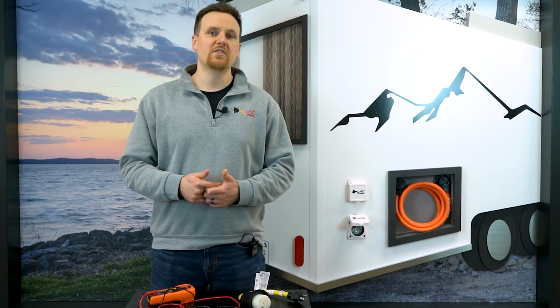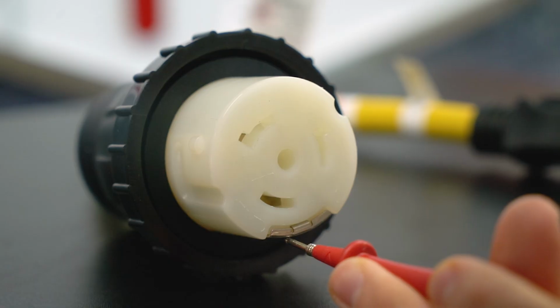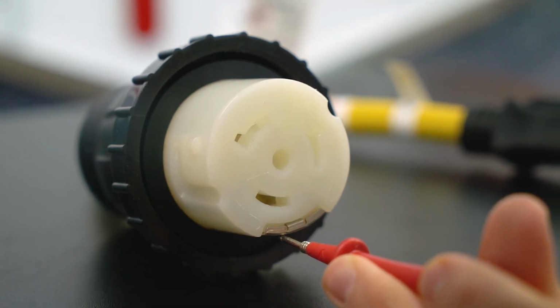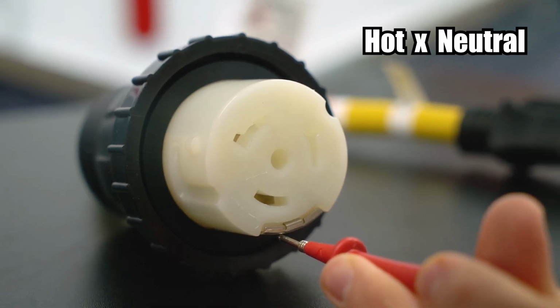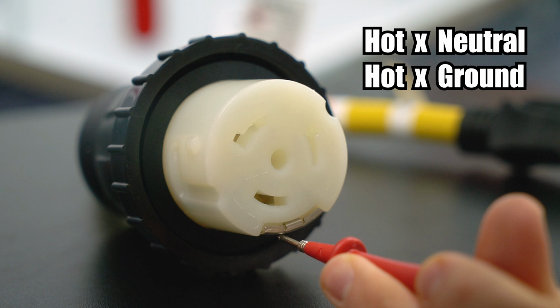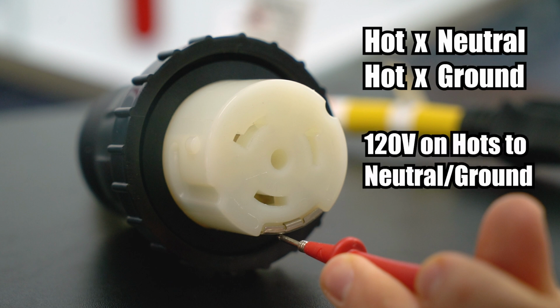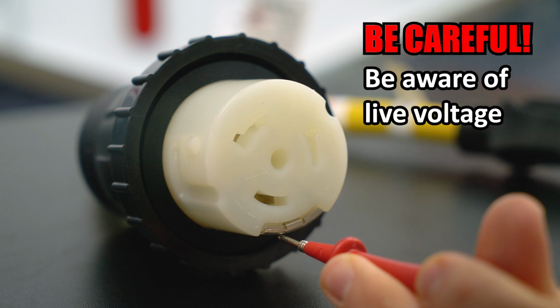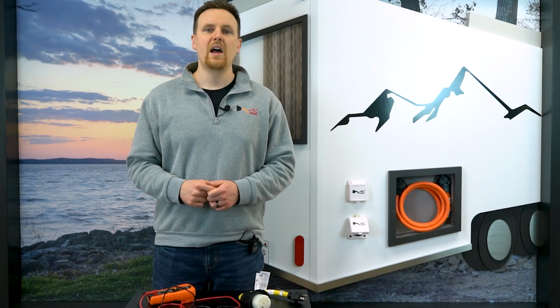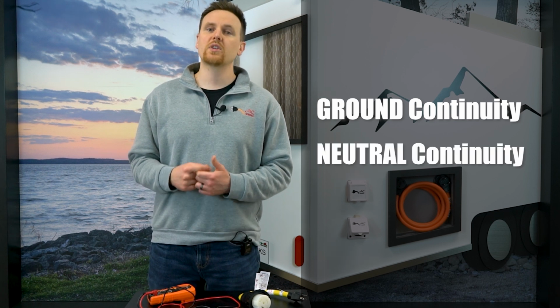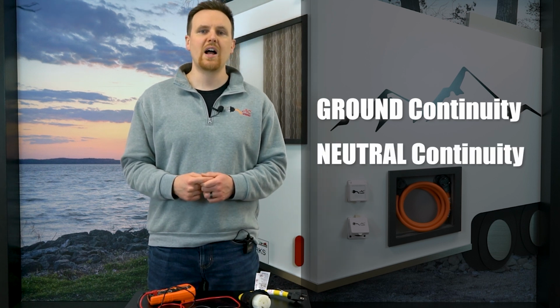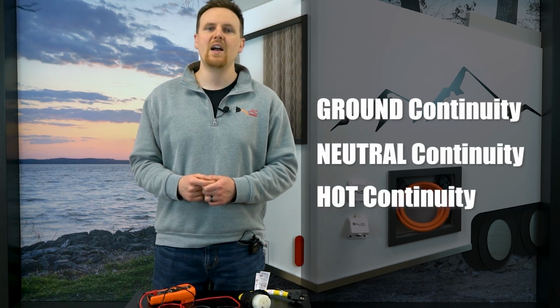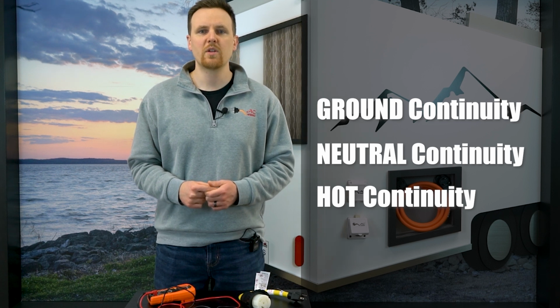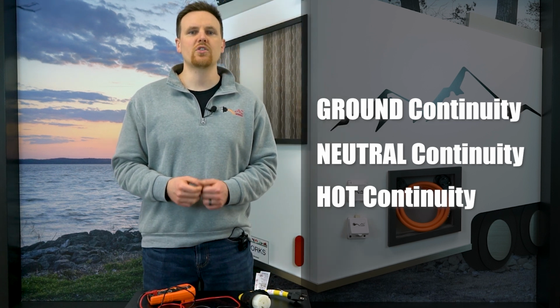If you are live testing to measure voltage, plug in the NEMA 5-15 side and measure voltage between hot and neutral, hot and ground. You should see approximately 120 volts on the bridged hots to the neutral and to the ground. Remember, always be careful and know what you're doing when working with live voltage. Now that we've tested ground continuity, neutral continuity, and verified that single hot is indeed feeding both hots on the SS2-50 end, we can be confident this adapter is functioning correctly.